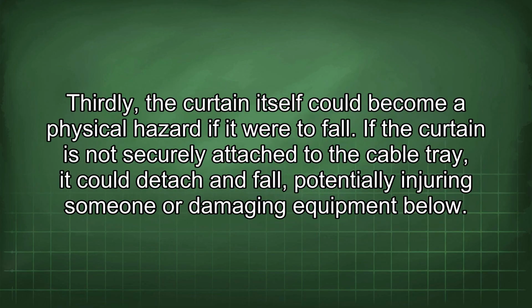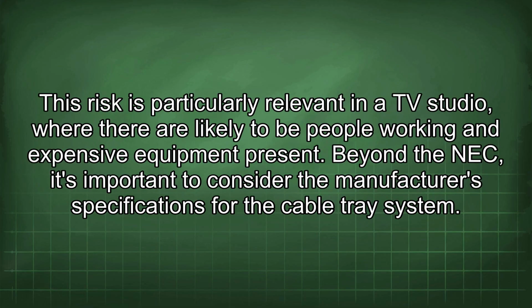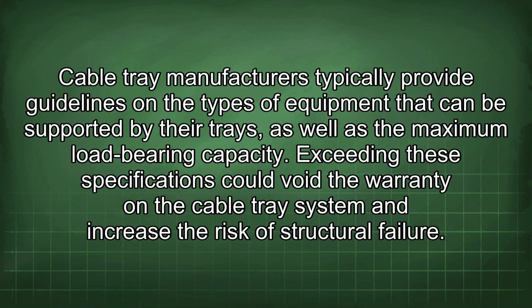Thirdly, the curtain itself could become a physical hazard if it were to fall. If the curtain is not securely attached to the cable tray, it could detach and fall, potentially injuring someone or damaging equipment below. This risk is particularly relevant in a TV studio, where there are likely to be people working and expensive equipment present. Beyond the NEC, it's important to consider the manufacturer's specifications for the cable tray system. Cable tray manufacturers typically provide guidelines on the types of equipment that can be supported by their trays, as well as the maximum load-bearing capacity. Exceeding these specifications could void the warranty on the cable tray system and increase the risk of structural failure.